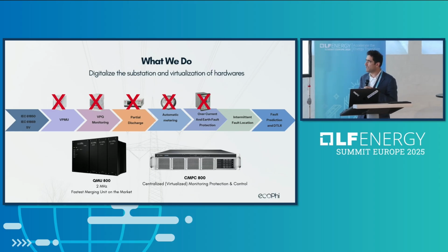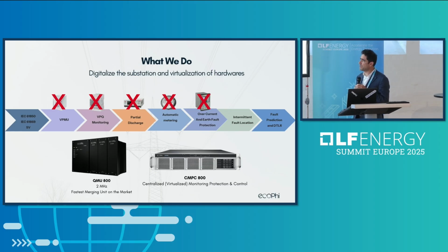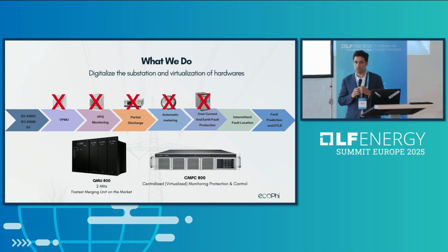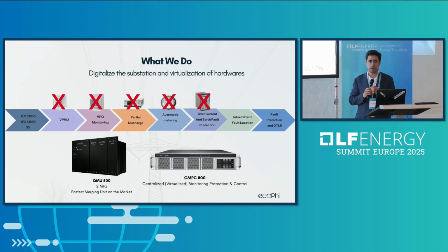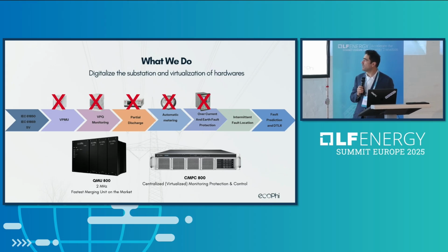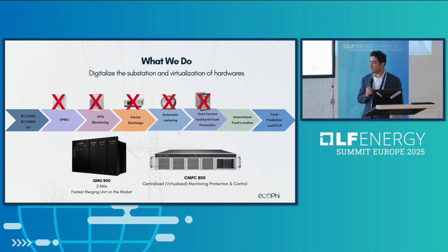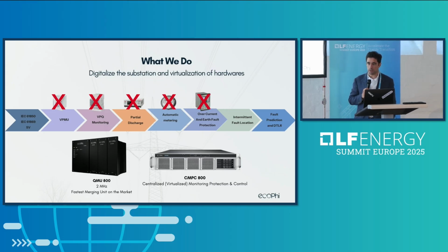Therefore, we developed the QMU 800, a merging unit that has the highest sample rate on the market, 2 million samples per second for voltage and current, and one of the highest resolutions as well, 24 bits per channel. We sample voltage and current according to IEC 61850 or 61869.